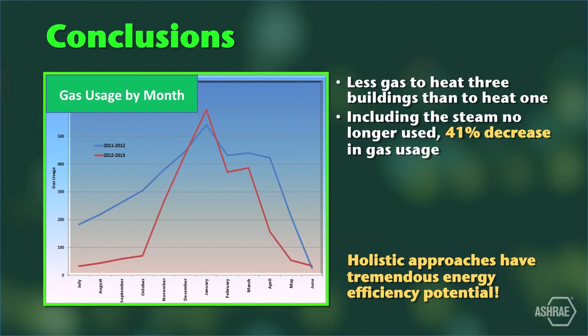We did not meter electricity, and clearly electric use at science went up due to the heat recovery chiller and the extra pumps. But it is a legitimate argument to say that the electric increase was minimal because the heat recovery chiller was running to make chilled water that the campus needed and used, and the pumps would have been running anyway, whether they were located in the science building or the academic center.